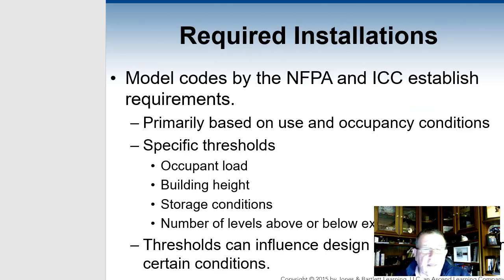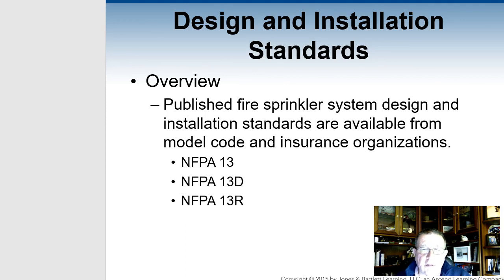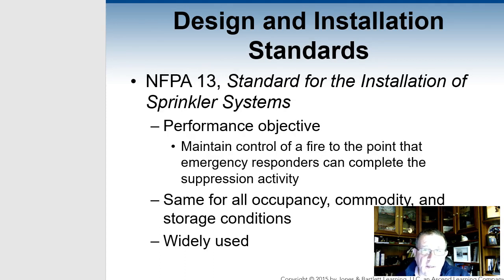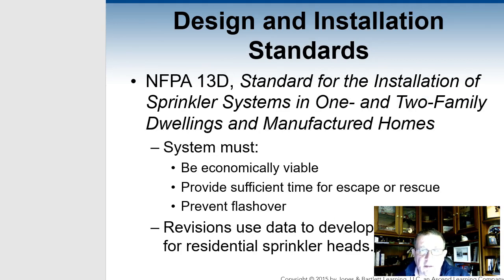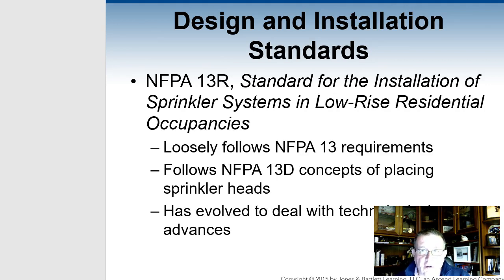We get into requirements about NFPA and then the ICC code. Occupancy load, building heights, and storage are all part of what goes into the design of a sprinkler system. The big thing is 13D and 13R are all part of the design mechanism under the NFPA code. And the big thing is how they have to perform and be maintained. The other thing is you've got installation systems in one and two family dwellings, and how they are designed through NFPA 13D. You also have 13R for low-rise residential housing, which is actually where we have the home sprinkler systems that we want to see out there today.